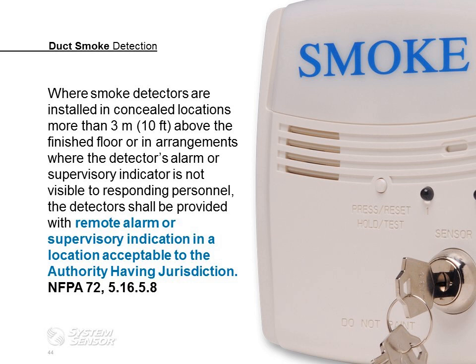And this is an important one that gets missed a lot. It's really important, and we are trying to get this message out to everyone. Where smoke detectors are installed in concealed locations more than 3 meters or 10 feet above the finished floor, or in arrangements where the detector's alarm or supervisory indicator is not visible to responding personnel, the detector shall be provided with remote alarm or supervisory indication in a location acceptable to the AHJ. So most duct detectors, by default, by their nature, are going to be greater than 10 feet above the finished floor. Duct detectors installed on a rooftop, obviously, responding personnel can't see those indicators. So we know per the standard you have to have some type of remote indication.